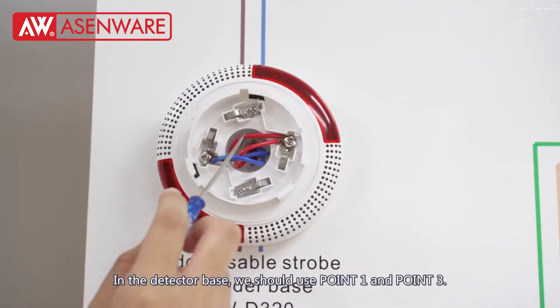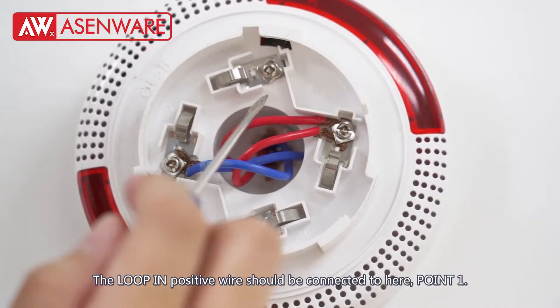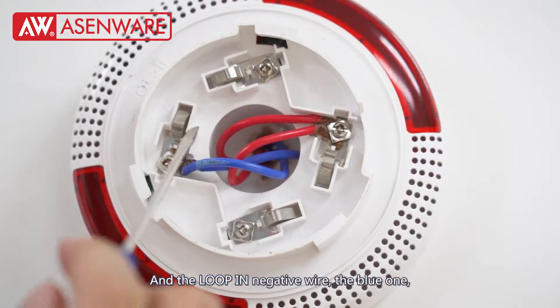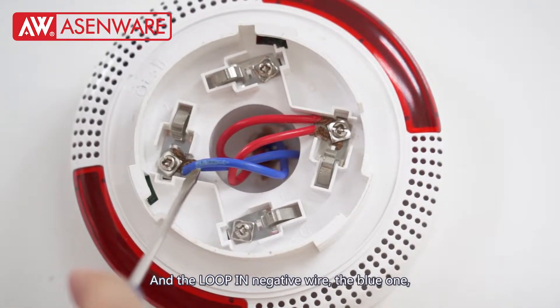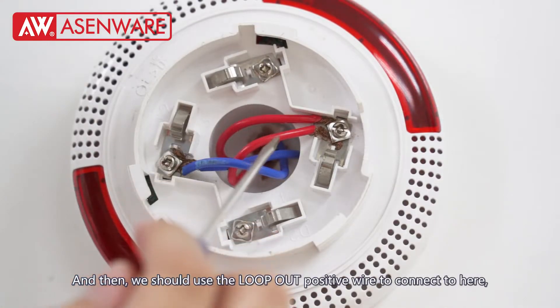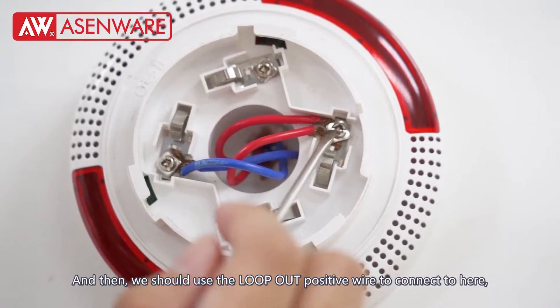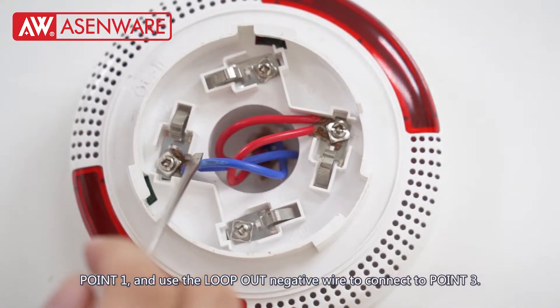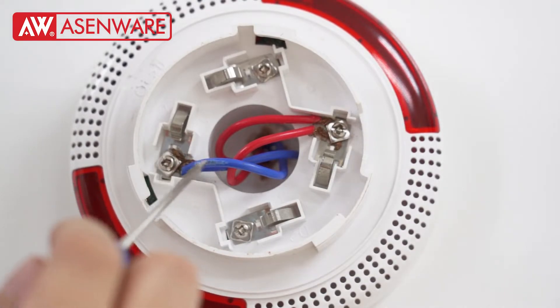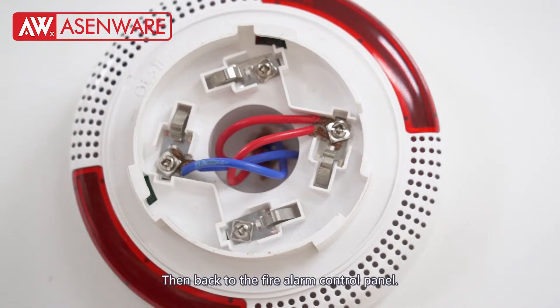In the detector base, we should use POINT 1 and POINT 3. The LOOP IN positive wire connects here at POINT 1, and the LOOP IN negative blue wire connects at POINT 3. Then the LOOP OUT positive wire connects at POINT 1 and LOOP OUT negative at POINT 3. The LOOP OUT wire connects to the next devices and then back to the fire alarm control panel.